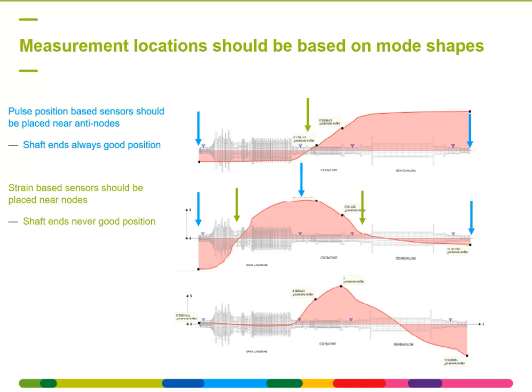So the blue color demonstrates where you should position the pulse position sensors. These should be placed on locations where you have high torsional vibration amplitudes. So for the top figure, where you have the lowest vibration mode, these would ideally be placed at the shaft ends. There you have the highest torsional vibration amplitude.